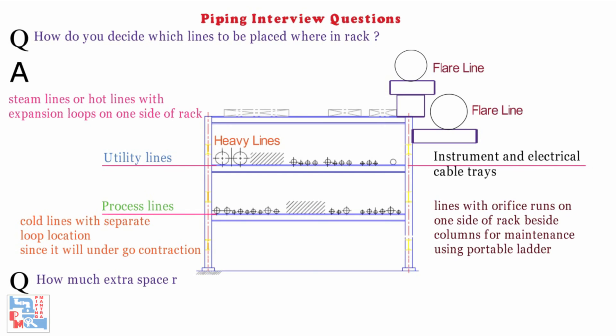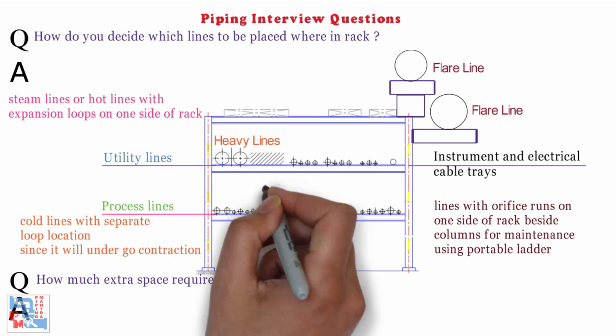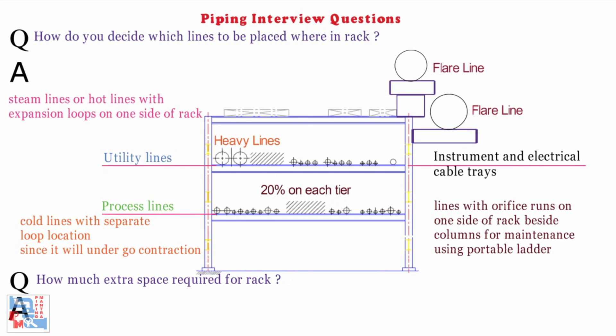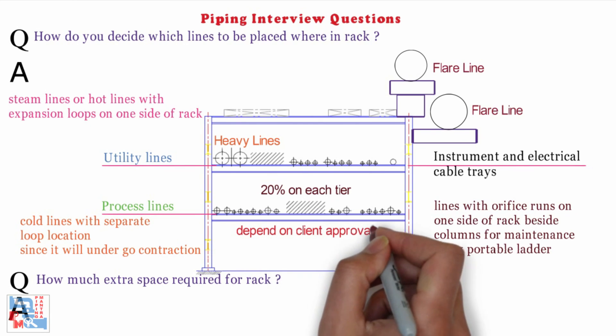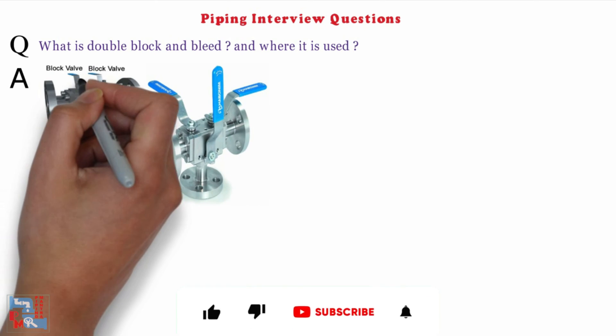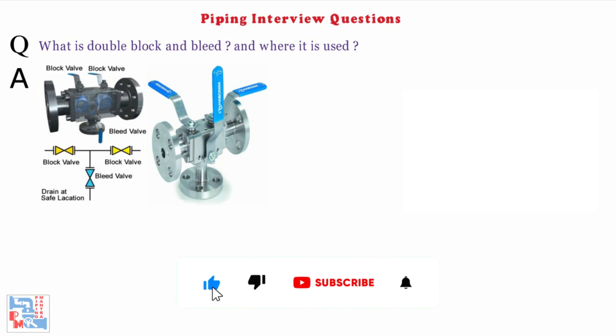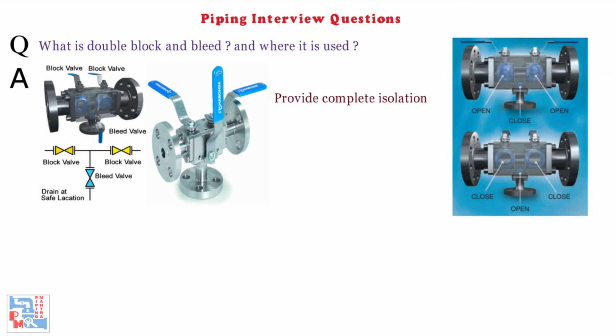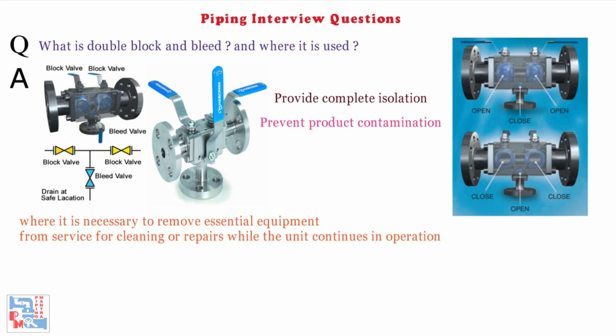Next: How much extra space is required for rack? Usually, 20% of extra space is required for future lines on each tier, but it all depends on the client approval and requirement. Next: What is double block and bleed and where is it used? Two block valves with a bleed ring in between, with a bleed valve connected to the hole of the bleed ring to provide complete isolation. Mostly, it is used to prevent product contamination or where it is necessary to remove essential equipment from service for cleaning or repairs while the unit continues in operation.